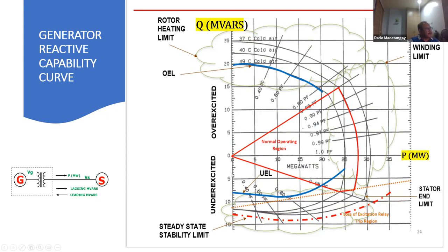Now, when the system has so many megavars on it, and the generator needs to absorb megavars, because, for example, at night the voltage is very high, those megavars need to be disposed of, so the generator needs to absorb them. Therefore, the generator is operating in the under-excited portion of the reactive capability curve, from zero down here. These are all limits that need to be considered in the protection system.